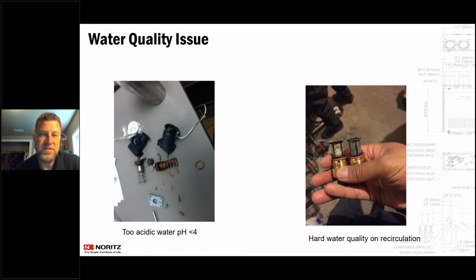So what we're looking at is something like a water softener, where it's actually removing the magnesium, calcium, or tripolyphosphate, Silifos, any kind of scale shield. All that scale shield is doing is coating the jagged ridges within those minerals, so they can't stick to anything in the system. It just goes through the system, so it won't stick to anything inside of our units. Right. Okay. Thank you. Yep, no problem. So any other questions on water quality?